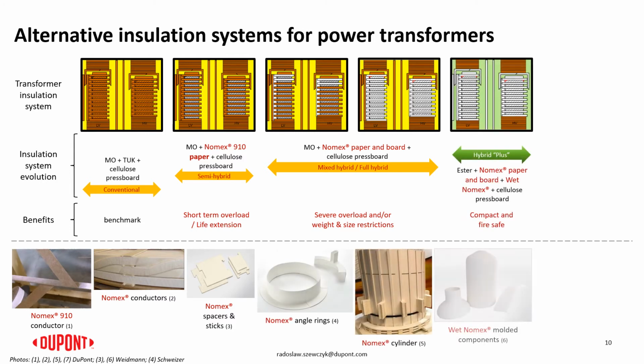When we look at the combination of insulation system with ester liquid, ester could allow higher operating temperature for the liquid, and then we may say that more insulation parts may be exposed to the higher temperature. So this sketch of the hybrid plus systems shows the Aramid insulation being extended to the barriers, to the winding cylinders, and even wet formed components which are located on the top of the winding.